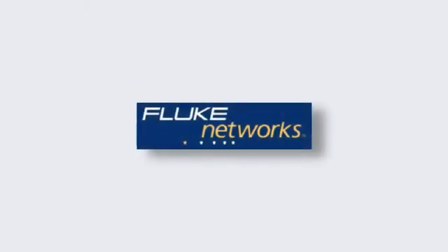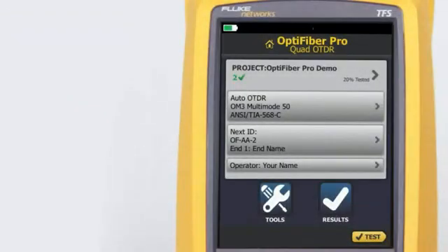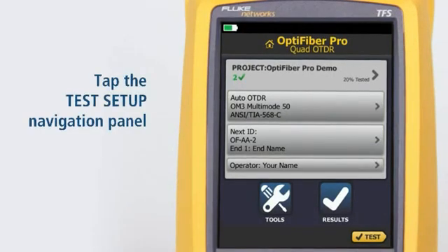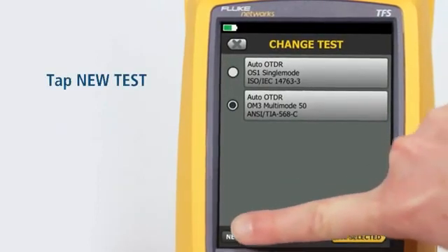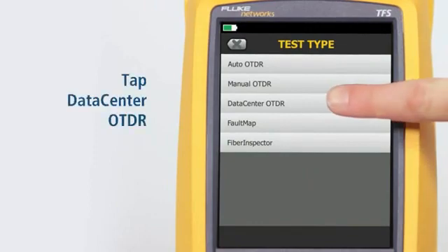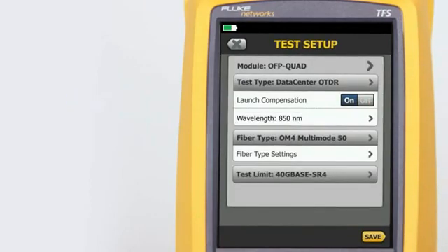Press the Home button — we're ready to run a test. The Data Center OTDR test mode is optimized for fiber installations that have short links, many connections, and the possibility of large reflections. Tap the Test Setup navigation panel, then tap New Test, then tap Data Center OTDR. Note that the Data Center OTDR defaults to only 850 nanometers for multi-mode fiber and 1310 nanometers for single-mode fiber — these are the wavelengths typically used in data centers.